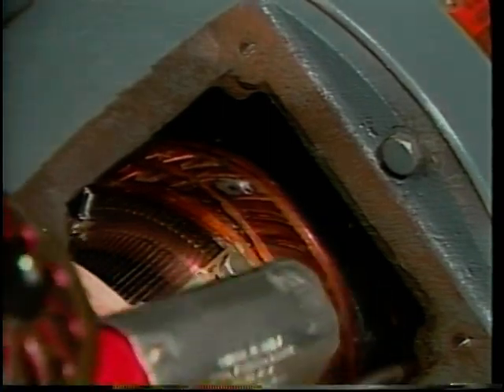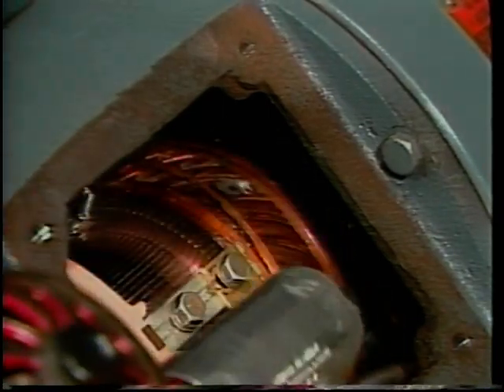Sometimes the problem indicated by a megohmmeter is not bad insulation, but moisture or dirt. Drying out a damp motor will raise the measured resistance considerably.